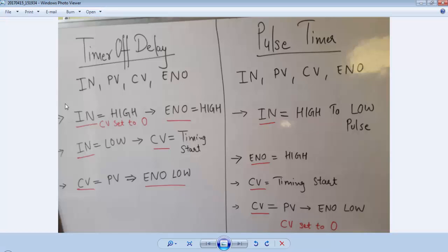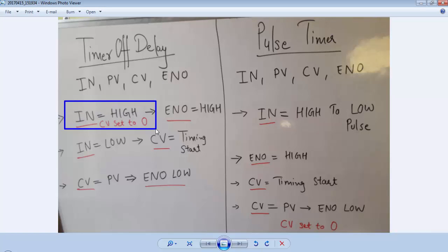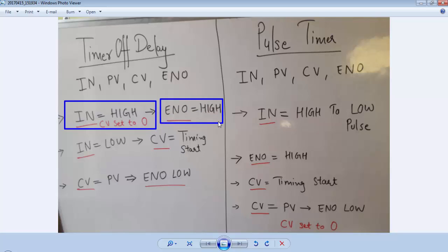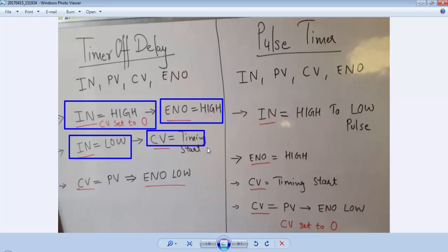From the simulation observation, when the input for a timer off delay is high, it will set the CV value to 0 and at the same time it will activate the ENO pin. The timer will not start its timing until we are releasing the input. When we release the input the CV will start counting the time and when CV is equal to PV then ENO pin becomes low and it will deactivate the output.